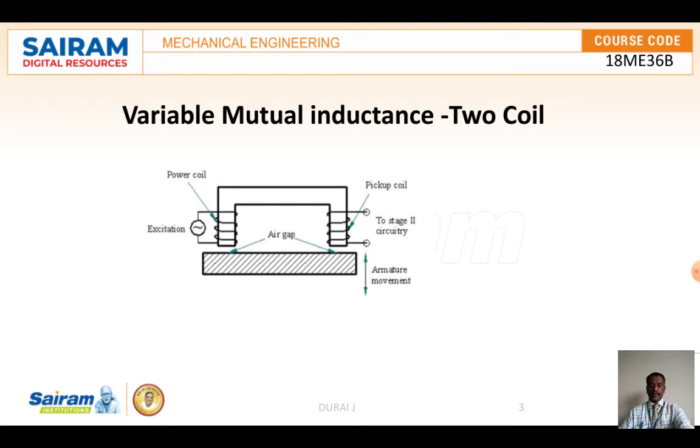The air gap between the core and armature governs the degree of coupling. In this figure, the detector portion is an electronic micrometer, with inductive coupling between the coils, which depends on the permeance of the magnetic flux path, changed by the relative position of permeable material. A variation of this can be used in a transducer for measuring small internal diameters.